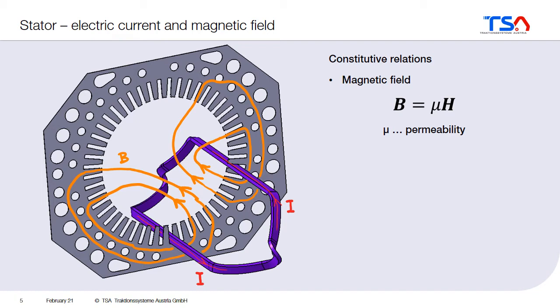Also the material is important. Here we see a cross section — again we have the coil with the current, now in this direction. In orange you see the magnetic flux lines. These magnetic flux lines, because of the material property — the high permeability of the magnetic steel sheet — the magnetic flux goes through the magnetic sheet. It does not go through the cooling ducts, which consist of air, and it also does not go through the slots. The slots consist of air, and the conductors in the slots are made of copper, which also has a low permeability. So the flux basically goes only in the magnetic steel sheet.